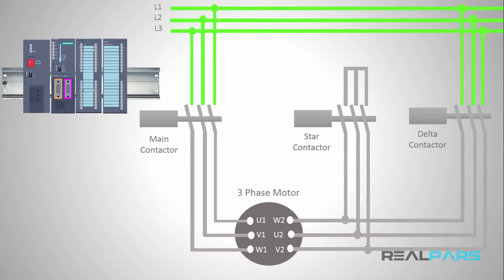For the PLC to be able to control the contactors I need to connect the contactors coils to the PLC's digital output module. I'll connect the main contactors coil to the first output, the star contactor to the second output, and the delta contactor to the third output of the DO module.